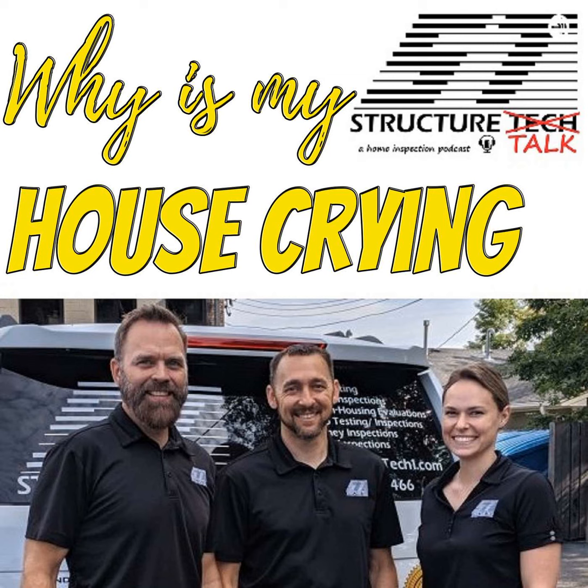I'll buy all that, Tess, but something that can be done—and I recommend this every time I see it during a home inspection—is when you've got that duct connected to your return ductwork, a duct that goes to the outside. We always recommend disconnecting that, because all it's going to do is pressurize your house, and it's not supplying combustion air to the room it's intended for. It ends up being a positive ventilation strategy, so I'd agree with you on that.